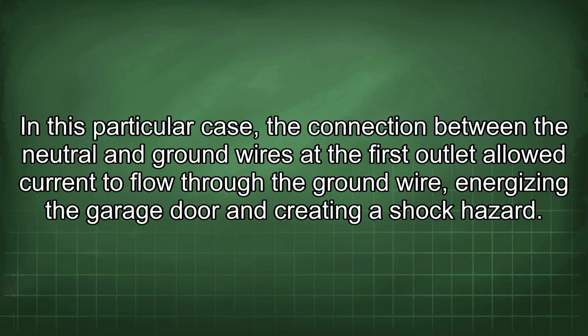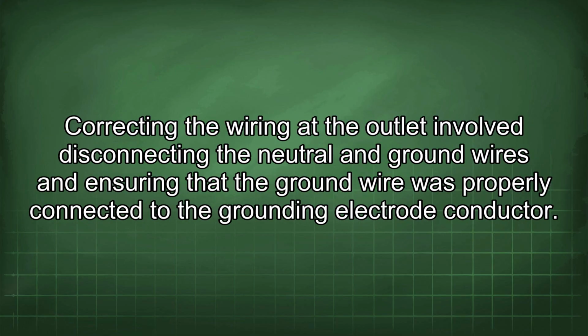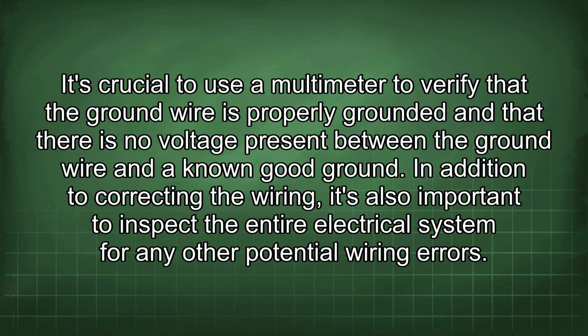In this particular case, the connection between the neutral and ground wires at the first outlet allowed current to flow through the ground wire, energizing the garage door and creating a shock hazard. Correcting the wiring at the outlet involved disconnecting the neutral and ground wires and ensuring that the ground wire was properly connected to the grounding electrode conductor. It's crucial to use a multimeter to verify that the ground wire is properly grounded and that there is no voltage present between the ground wire and a known good ground.